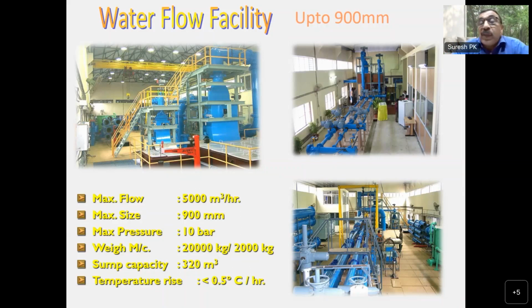The fallacy of this system is that if you want to make a total flow, like a PD meter you want to calibrate, and the PD meter has to be stopped to make a measurement, then you cannot stop the flow here. So therefore, you have to have another system which is called the standing start and stop method, where you can calibrate the PD meters and other kinds of things, where it is more important for you to find out the total volume rather than the flow rate at which it has happened.